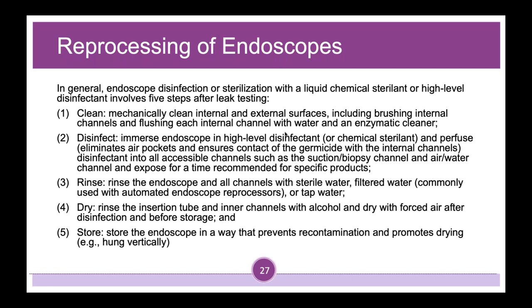Disinfect: immerse the endoscope in high-level disinfectant or chemical sterilant and perfuse disinfectant into all accessible channels such as suction, biopsy channel, and air or water channels, and expose for the time recommended for specific products.